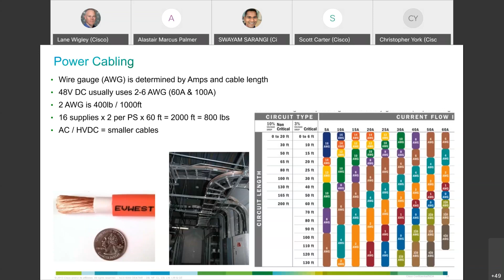For something more critical, you'd have a different tolerance. But you can see here, if we're talking about 30 amp links, which is what we usually have coming into our routers, running 30 to 40 feet, you get into this 2 AWG and 4 AWG range. Then you're talking about connecting 4 of those to each power supply, in some cases times 12 or 24 power supplies. You can very quickly get a lot of cable, and copper is very expensive and needs to be managed through these facilities. So this is one of the drivers to go to higher voltage. If we go to higher voltage in our systems, we can use lower amps, meaning the cables can be lighter, and it also means less power conversion has to be done before it comes to us.